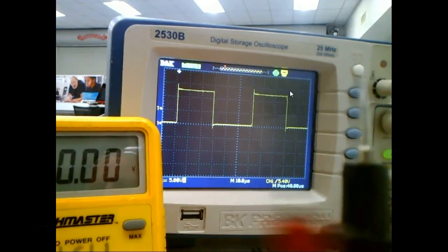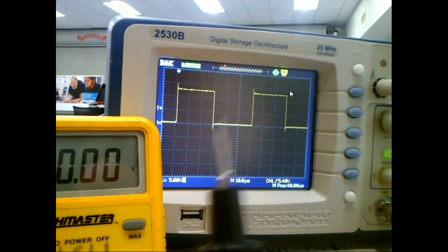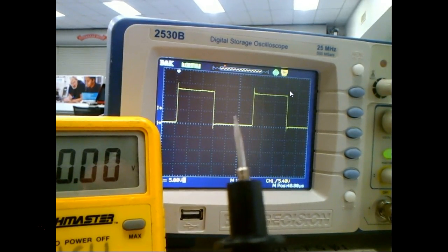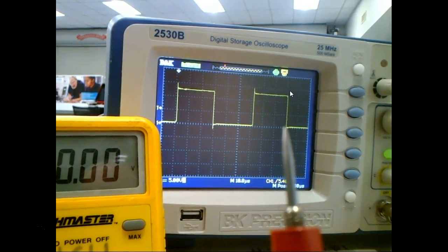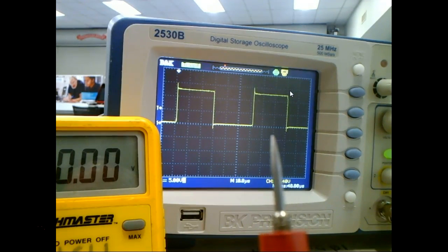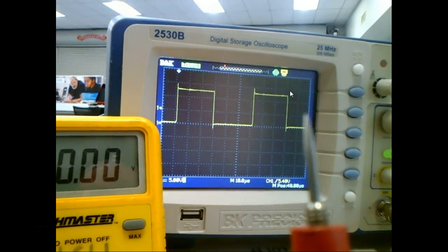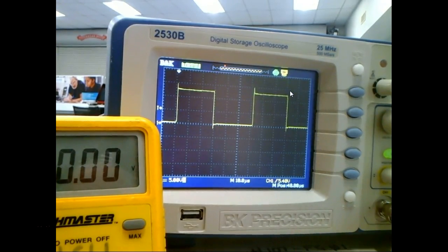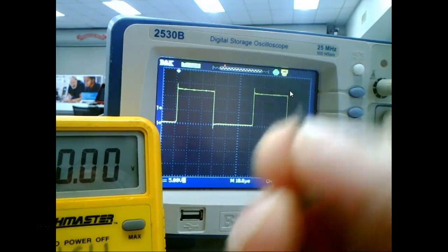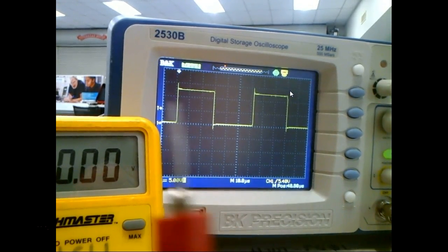What do we do when we normally troubleshoot? We take this sucker right here and we get an alligator clip and we clip it onto our common and troubleshoot relative to this, right? Which works out better because now I've only got one hand in the circuit. Most of your meters now have a cap that comes over here and tries to cover this up and avoid that. But you're going to see people taking things off all the time, which is not good.